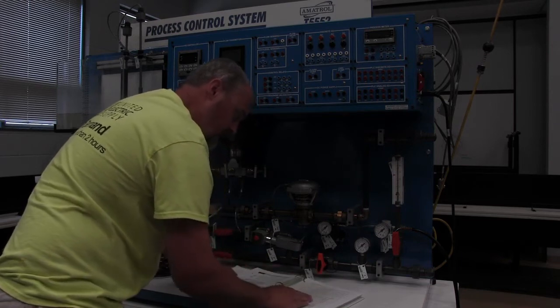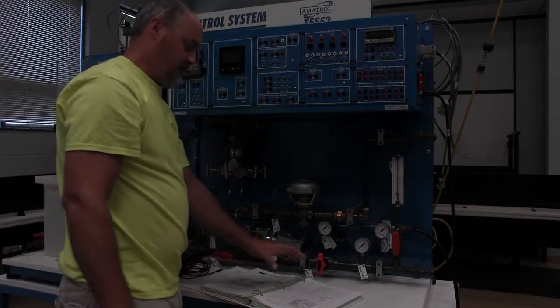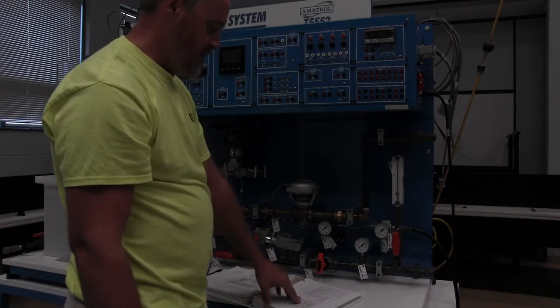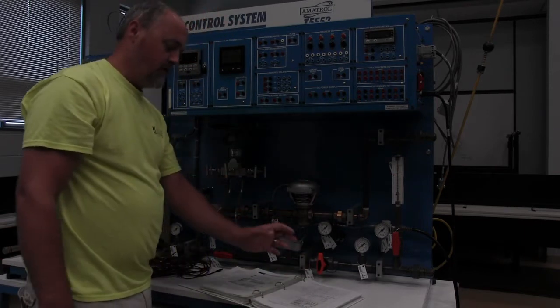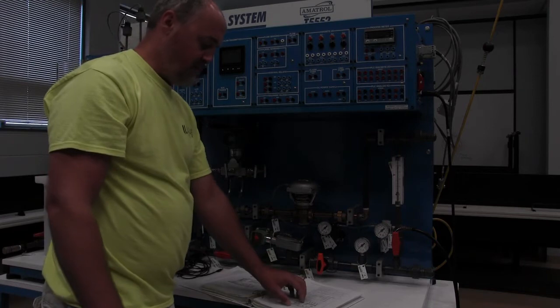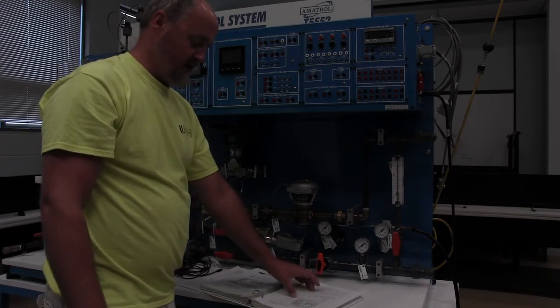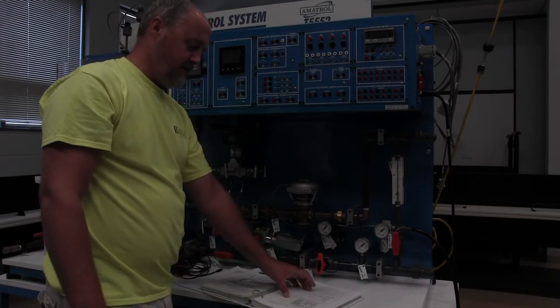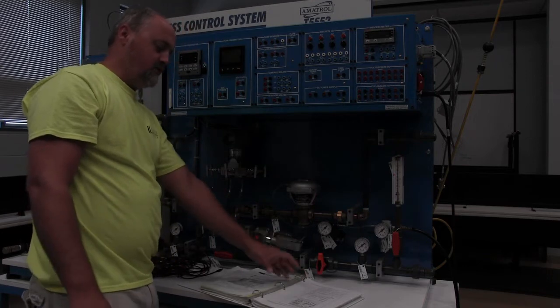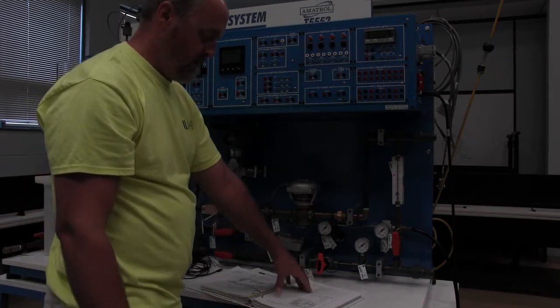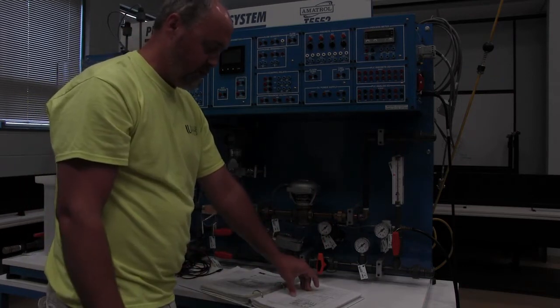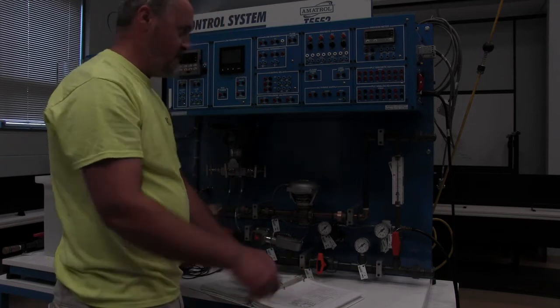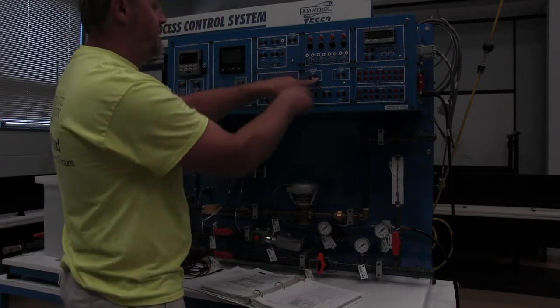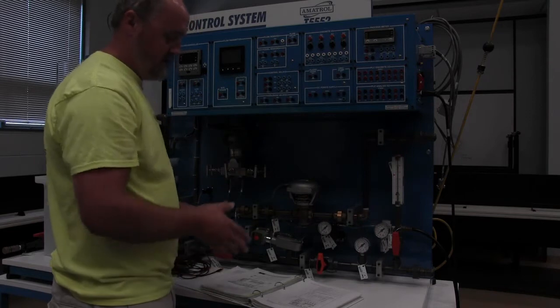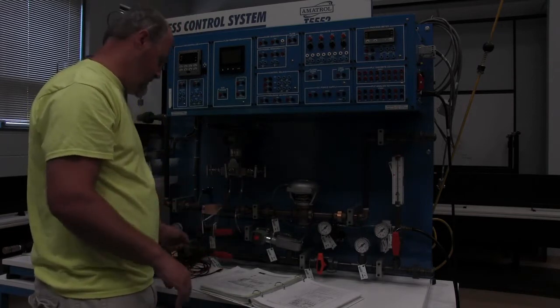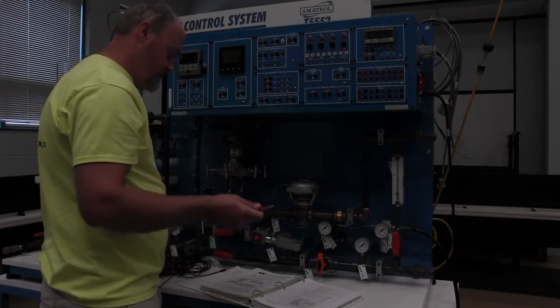Now we're going to connect as shown. This one's going to give us a ladder diagram and a wiring schematic. I really recommend that when you're wiring stuff, if you have a picture that says wire it like this and you have a schematic, try to wire off the schematic, because this is what you're going to see in the field when you're truly working. You're not going to have a picture that says put this wire here, move it over to here. You're going to see a diagram, and that's how you're going to trace it. So I'm going to go ahead and wire this up as needed.